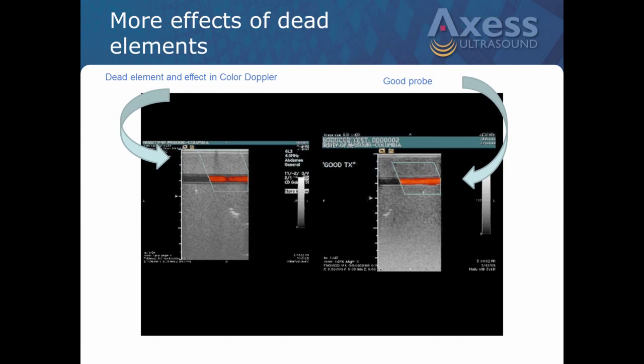Another question, from Chandra: how do you identify cable issues versus dead elements? Great question, and I'll touch on that in a few slides, but it comes down to being able to properly test the probe. At the level of clinical engineering, or looking at it on site, you really can't tell. But through proper evaluation of the probe, you can -- I'll share that with you in a minute.